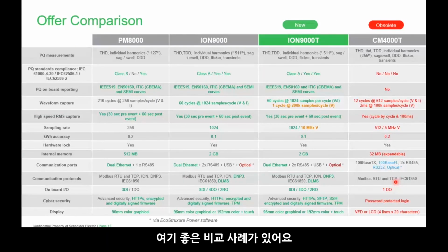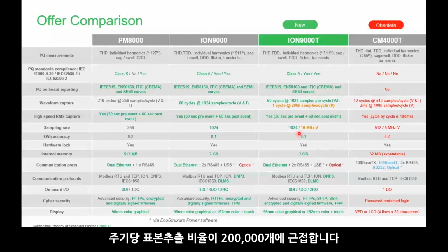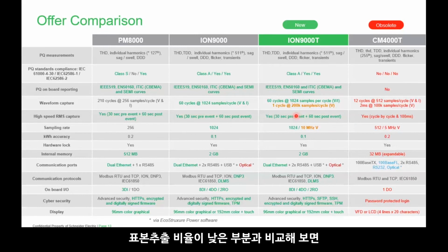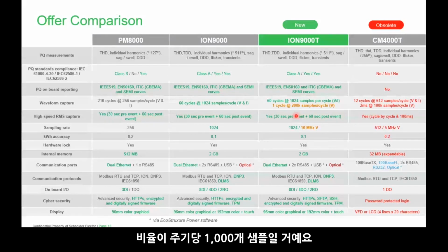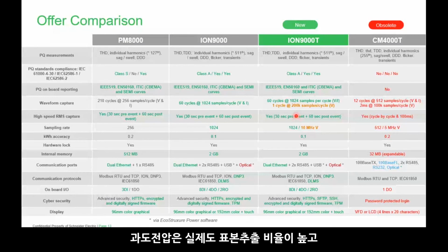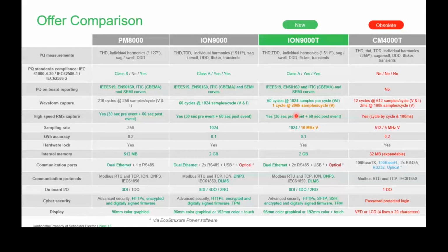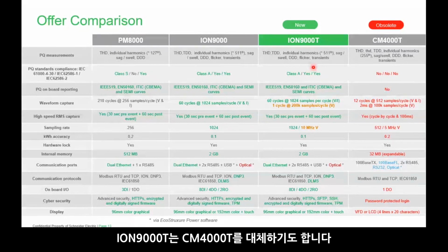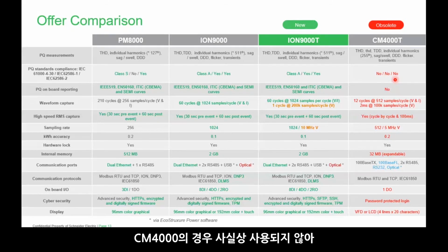This gives you a good comparison between the PM8000, ION 9000, and the ION 9000T, the transient type. As you can see in the highlights in orange, the sampling rate per cycle is close to 200,000 samples, compared to the lower sampling rate, which is probably 1,000 samples per cycle. So the transient meter has a high sampling rate and captures the real transients happening on the network. This ION 9000T is also substituting the CM4000. We used to have the CM4000 transient meter, but this product is already obsolete, and it has been replaced by the ION 9000T.